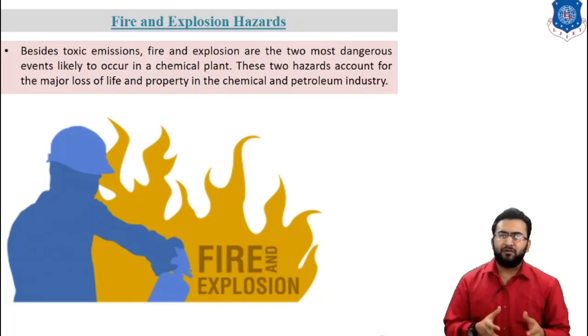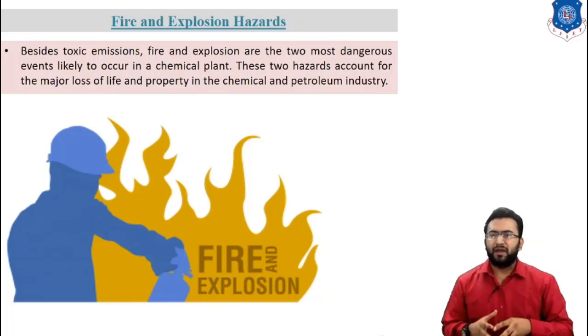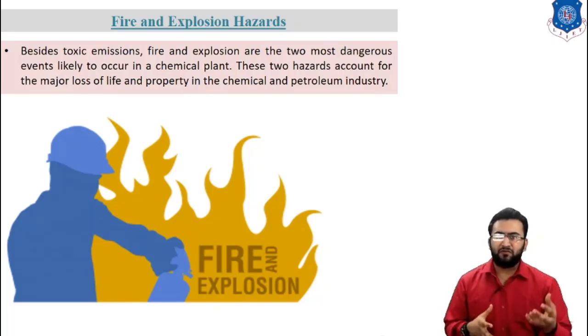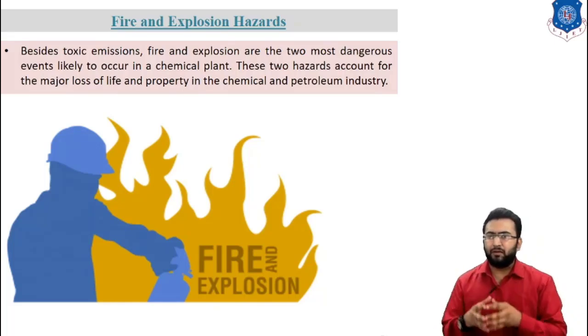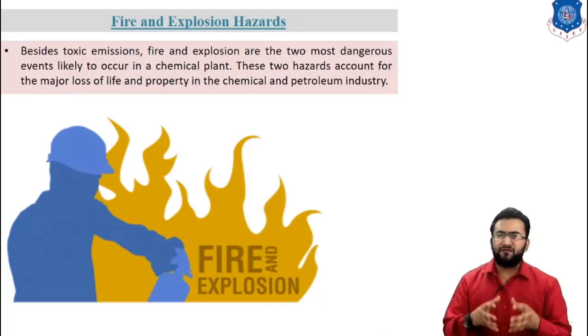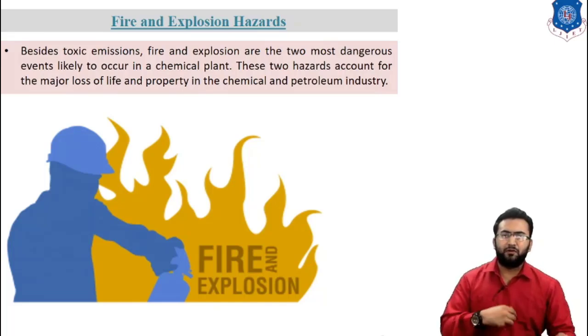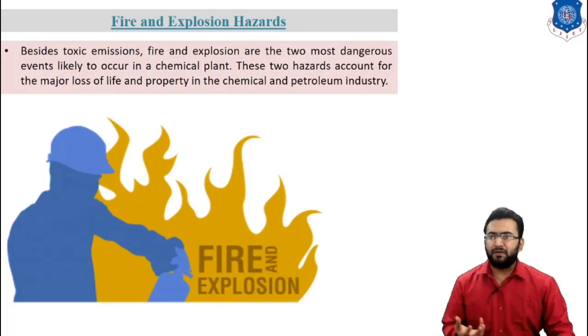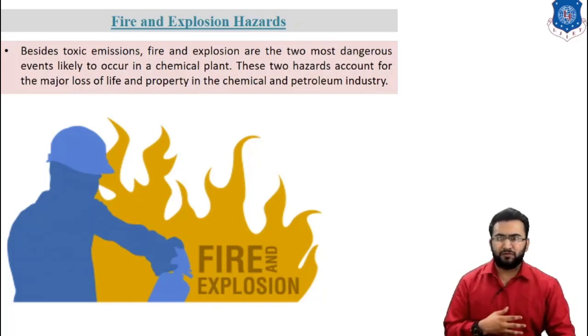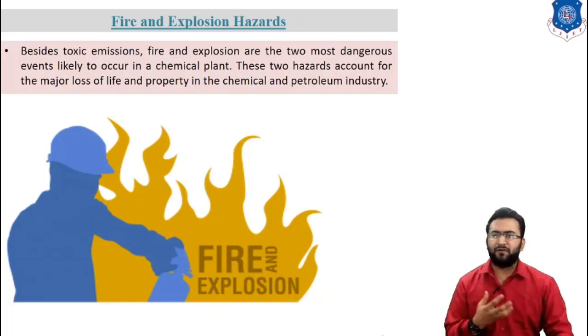Hazardous operations should be isolated by location in a separate building or by the use of a brick firewall. Brick or reinforced concrete walls can be designed to limit the effect of an explosion, particularly if the roof is designed to lift easily under the explosion force. So this is all about fire and safety.